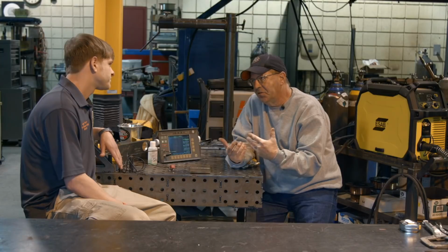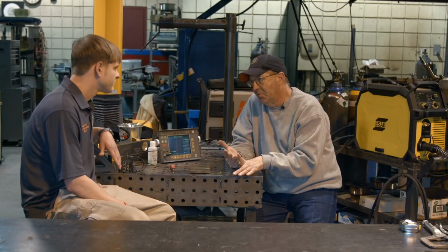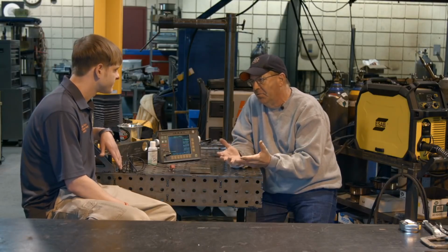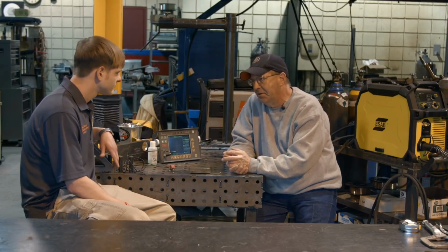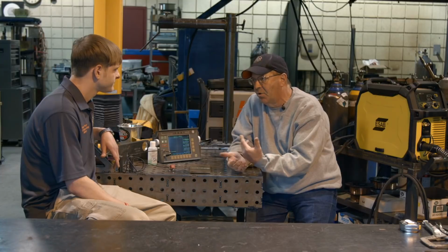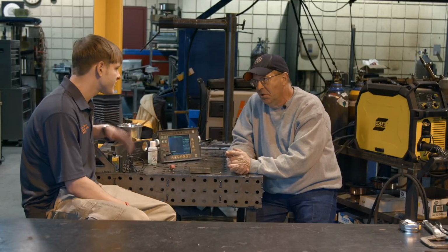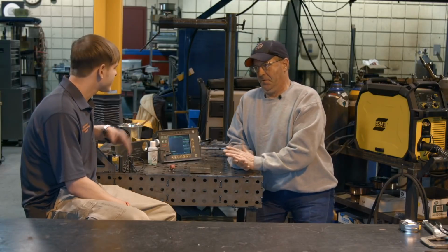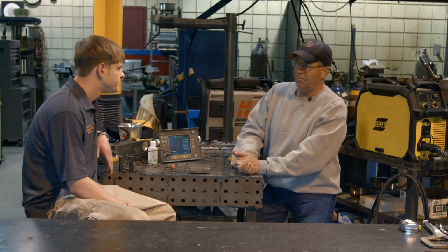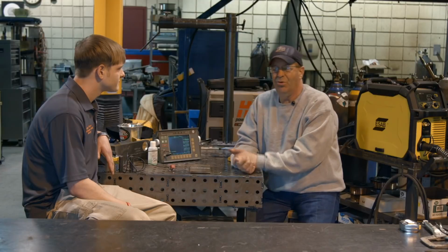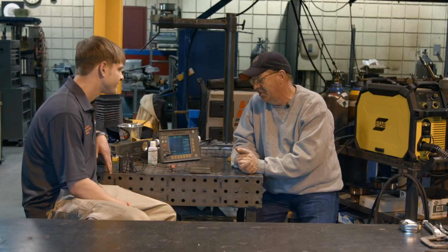So in my instance, I've got a piece of 10-inch Schedule 40 pipe. We know what the wall thickness of that was when it was put in. We can go look that up. Yes, sir. But then they're getting a reading that says it's 0.128. Now we know that there's internal corrosion on the inside of that, and we no longer have our true wall thickness. And under pressure, with crude flowing through there, it's not the cleanest. We've got some sand in there, it'll erode away very quick. I've been around some areas where I'm reading those UT, I look by, I'm going, you know what's flowing through there under high pressure, like you said.